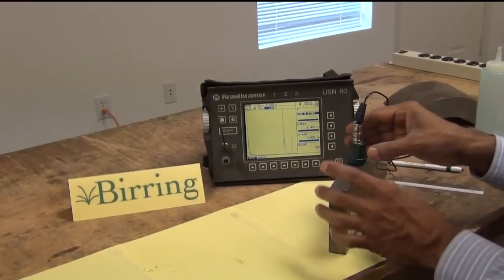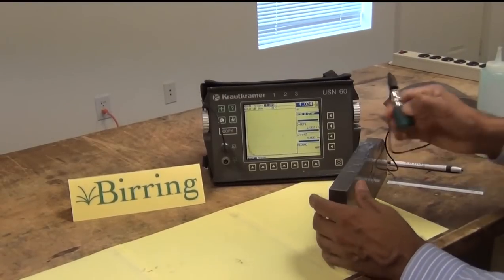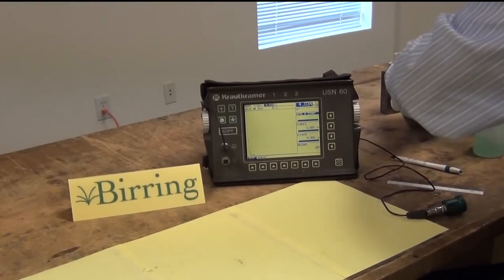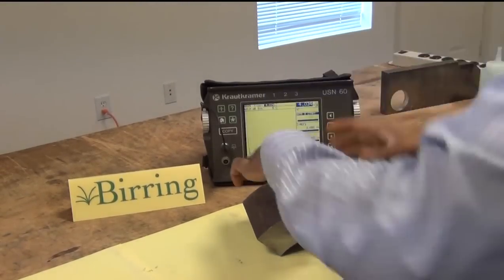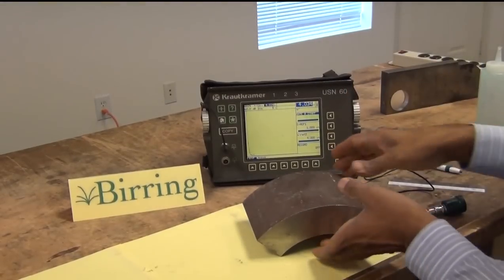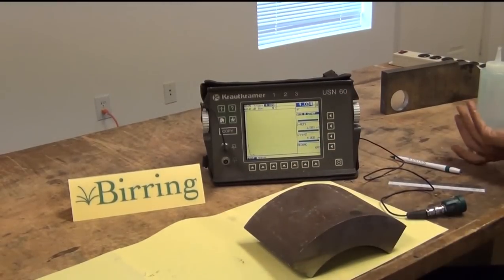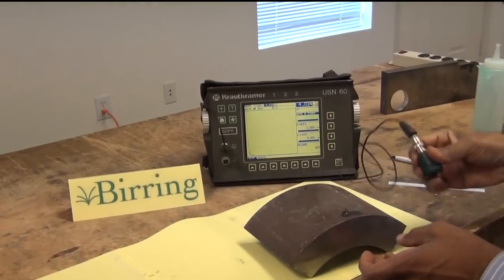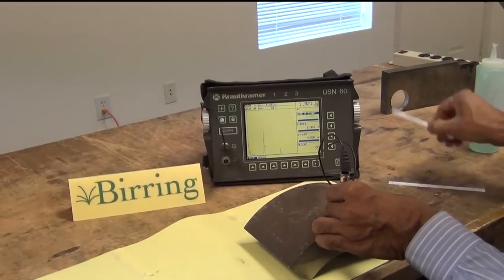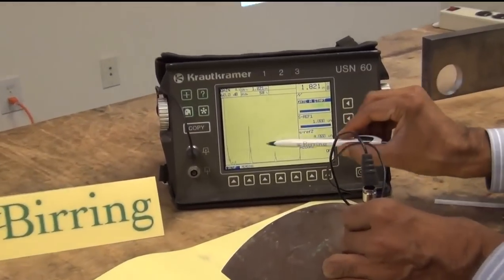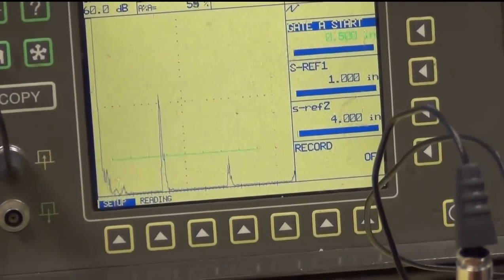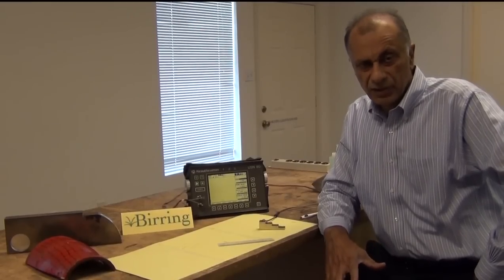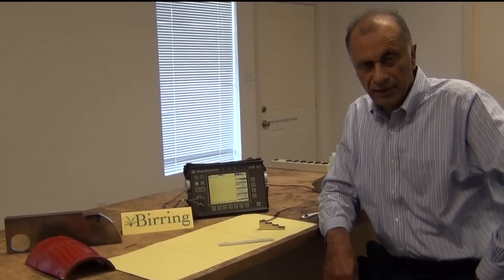So that completes the calibration with the single probe and if I have to take a measurement for example on this thick piece which looks like about 2 inches. So we apply the couplant again and put the probe and here we go the signal is here right there and the thickness being measured is 1.821 inches. That was a brief description of the calibration process for thickness measurement.